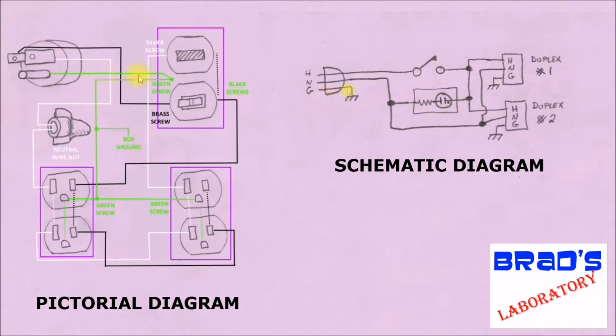Ground, I brought in the ground wire. I tied it to the ground lug on the switch, and then I followed that down with some bare copper wire—it wasn't green, just bare copper. It goes to the box and gets grounded to the box, and then it goes down to the two outlets. The way the current runs is it comes in through the hot, through the switch.